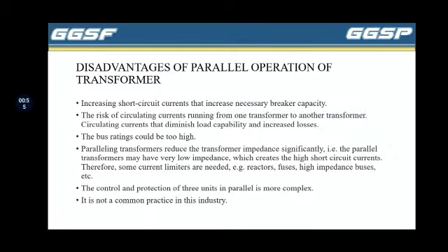Disadvantages of parallel operation of transformers: increasing short circuit current, which increases the necessary breaker capacity; the risk of circulating current running from one transformer to another transformer, and circulating current reduces load capability and increases losses. The bus rating could be high.